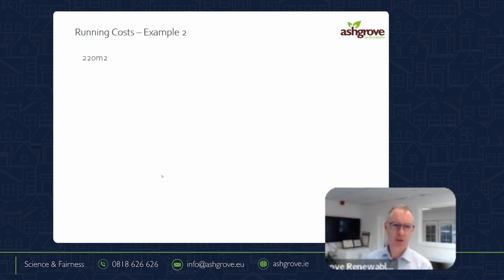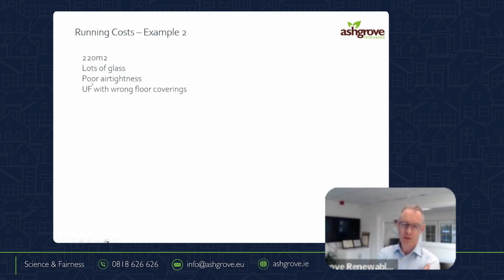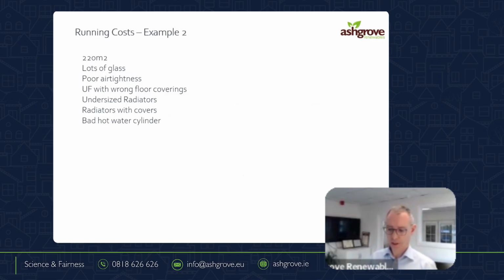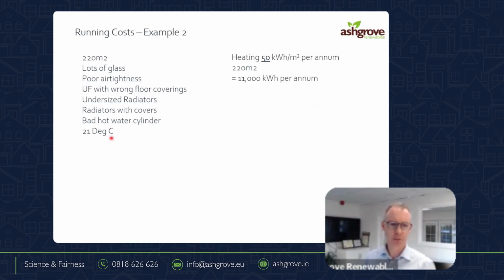However, similar scenario, same size house, lots of glass, poor air tightness. This historically would have been dormer houses, typically were extremely poor on air tightness. Underfloor heating with the wrong floor coverings or something dramatically wrong, pipes wrong, so on. Undersized radiators, covers on the radiators, the same as throwing a duvet up on it. Well done. The wrong hot water cylinder, or in this case, we've just chosen 21 degrees here for the heating, so we haven't even ramped the temperature up, which in some cases, I think the highest we've seen in the last 10 years, maybe 27 degrees.